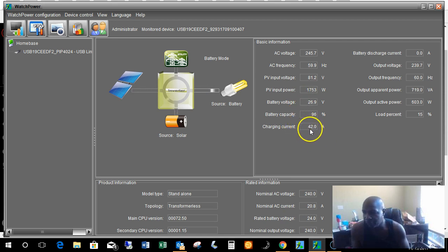We're bringing in 42 amps, which gets converted via MPPT. It brings down the voltage — the string voltage is about 110 — down to whatever the battery voltage is, and it increases the amps available to charge those batteries. Right now we have no discharge.